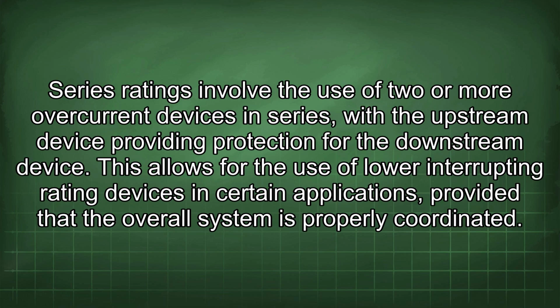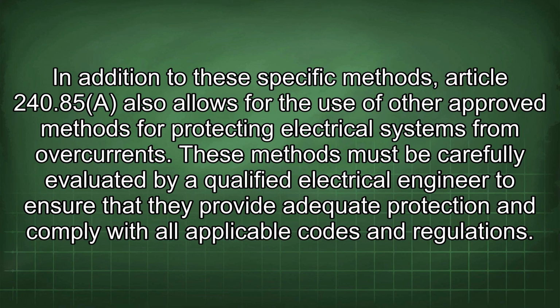Series ratings involve the use of two or more overcurrent devices in series, with the upstream device providing protection for the downstream device. This allows for the use of lower interrupting rating devices in certain applications, provided that the overall system is properly coordinated. In addition to these specific methods, Article 240.85 also allows for the use of other approved methods for protecting electrical systems from overcurrents. These methods must be carefully evaluated by a qualified electrical engineer to ensure that they provide adequate protection and comply with all applicable codes and regulations.